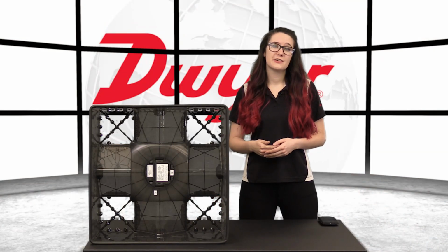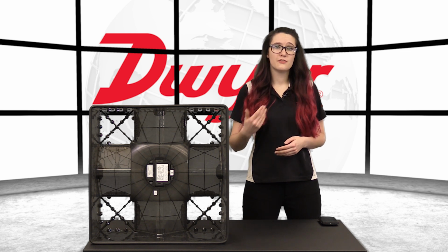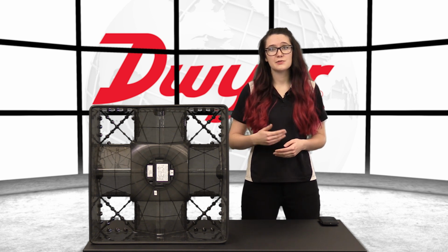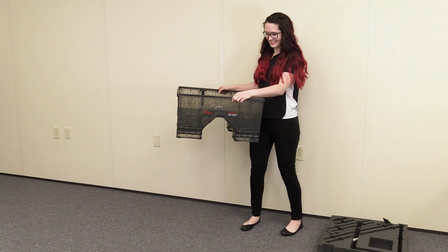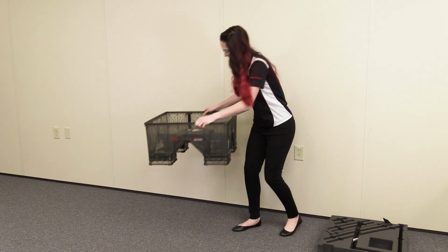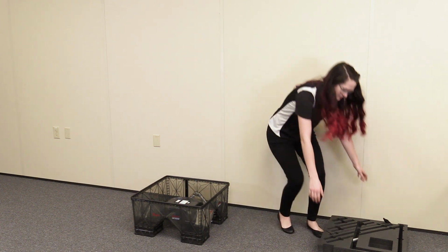It's important to zero your hood in order to ensure accurate measurements. We recommend you zero your hood before you start balancing for the day, as well as when switching between ceiling and sidewall air measurements. To zero for ceiling diffuser readings, place your hood on the ground so all 4 pitot arrays are making contact with the floor.